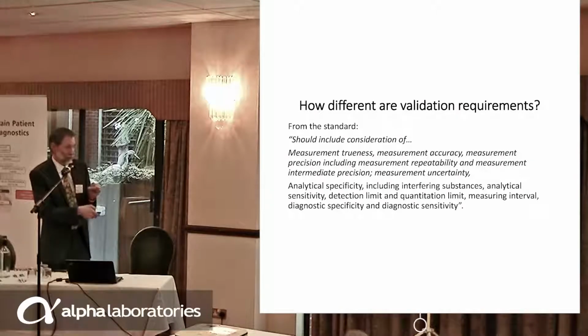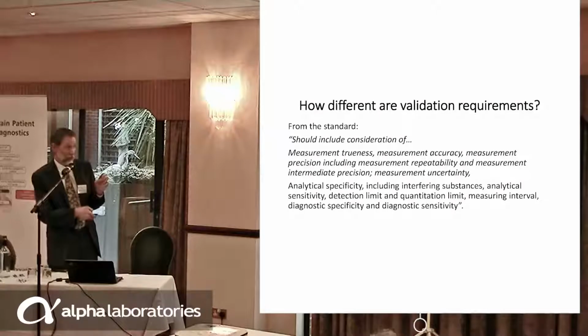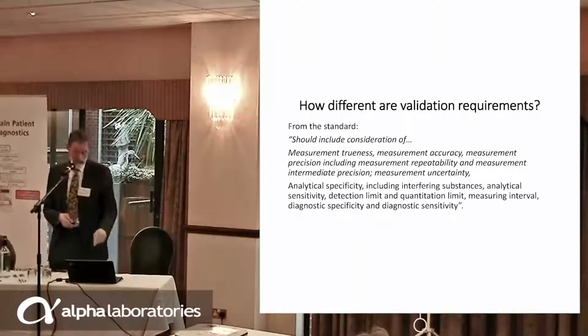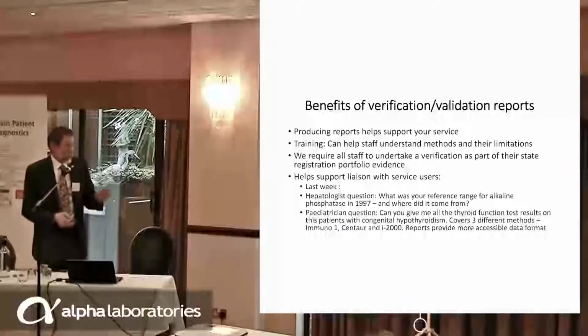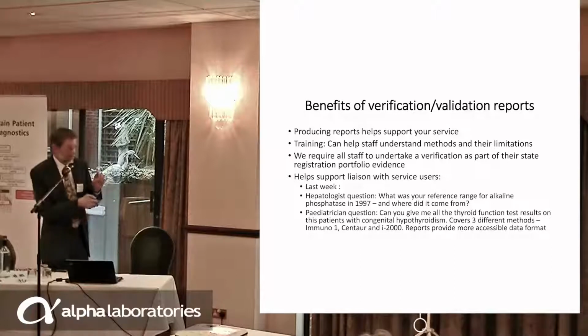But measuring interval: what's your lower limit, what's your upper limit, what's your detection limit, what's the quantitation limit, and potentially things about diagnostic specificity and sensitivity. Okay, so that's from the standard. I'm not going to say much more on validation, other than to say you will need to put a little bit more data in there, dependent on the type of method it is.